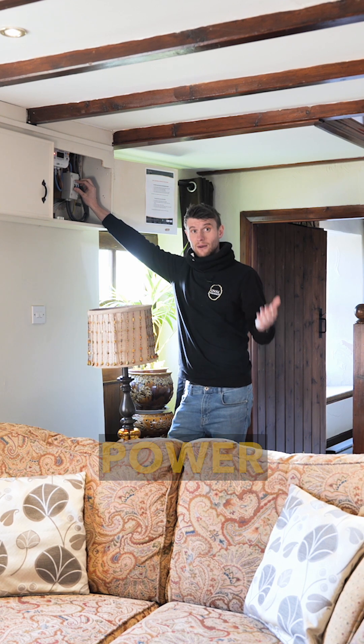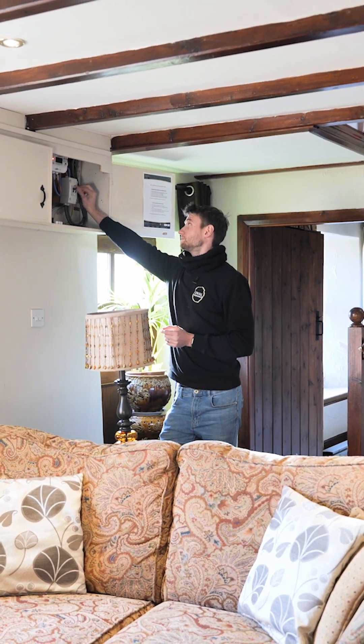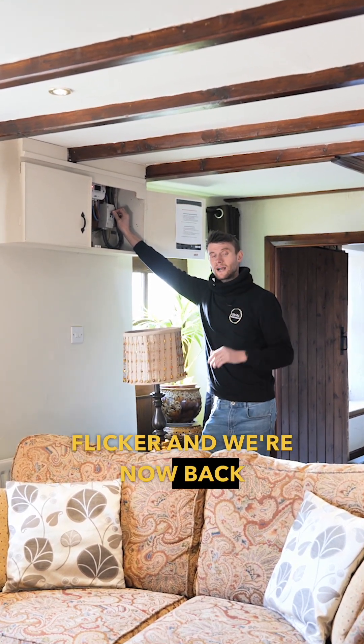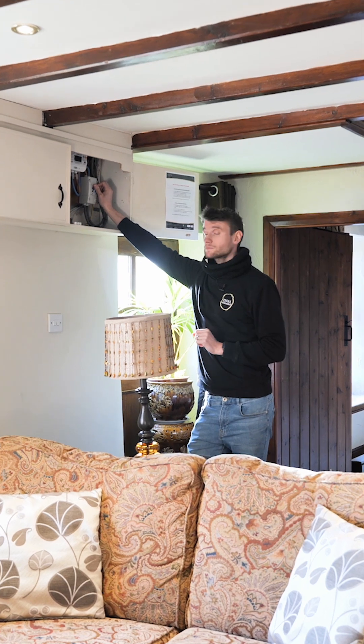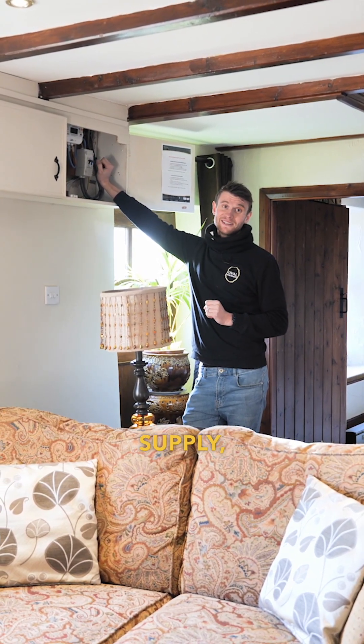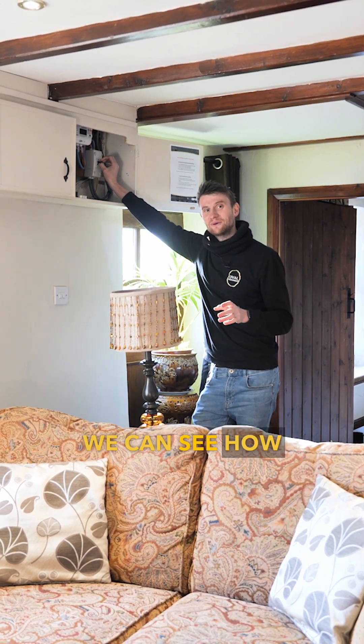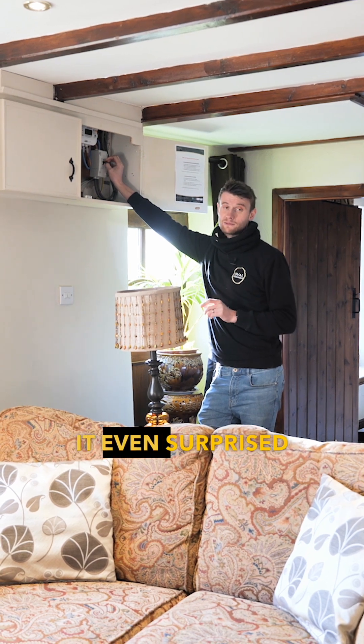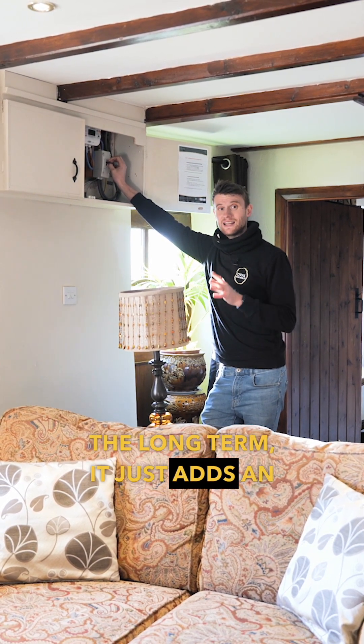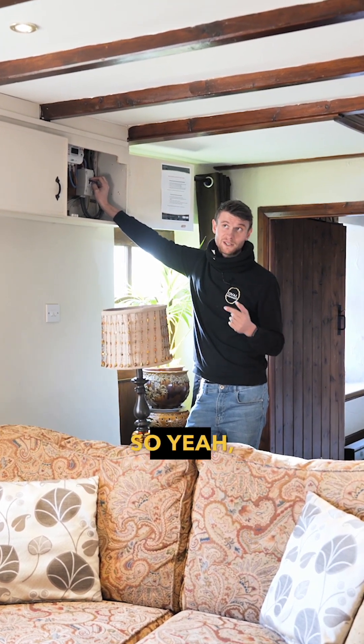If I turn this back onto the grid — simulating the power being reinstated — let's see what we notice. There we go, just a really small little flicker and we're now back onto the grid supply. The customer's probably now got a notification to say they're back on the grid, which I'm going to text him about. You can see how quickly that changeover happens — it even surprised me this time. Long term, it just adds extra functionality to the system, so you get more for your money. That is the backup system.